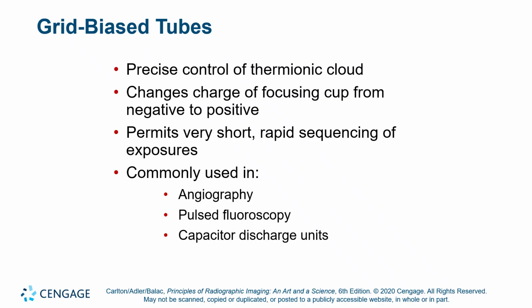And so if you're making an exposure and the high voltage is on, but the focusing cup is constantly flipping, when the focusing cup is negative, you'll make X-rays. But when the focusing cup is positive, the positive focusing cup grounds out the available space charge, and you don't make X-rays because none of the electrons end up rocketing over to the anode, because they have a faster pathway grounding out on the positive focusing cup. So as fast as you can flip the polarity of the focusing cup, that's how many bursts of X-rays you can create per second. And so if you connect it up to a high frequency AC wave, your focusing cup is going to give you a high frequency X-ray pulse like a machine gun.